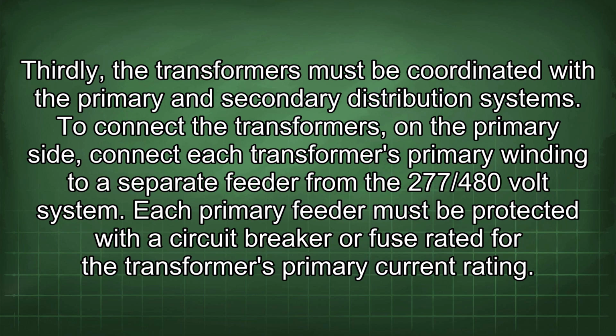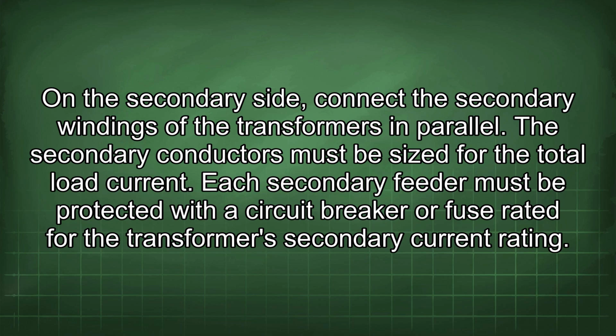To connect the transformers, on the primary side, connect each transformer's primary winding to a separate feeder from the 277/480 volt system. Each primary feeder must be protected with a circuit breaker or fuse rated for the transformer's primary current rating. On the secondary side, connect the secondary windings of the transformers in parallel. The secondary conductors must be sized for the total load current. Each secondary feeder must be protected with a circuit breaker or fuse rated for the transformer's secondary current rating.